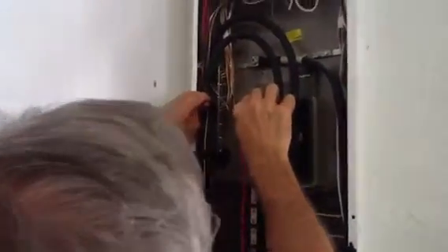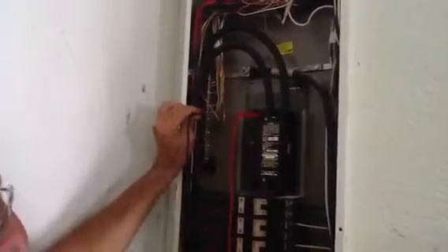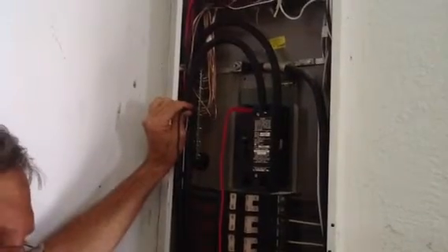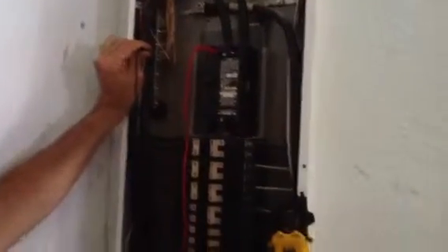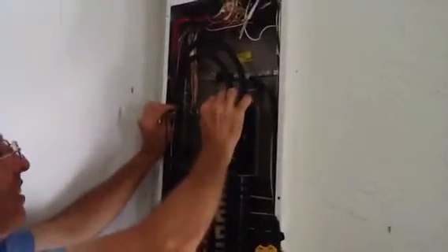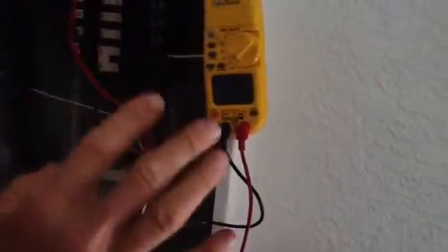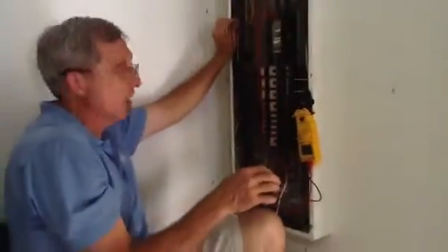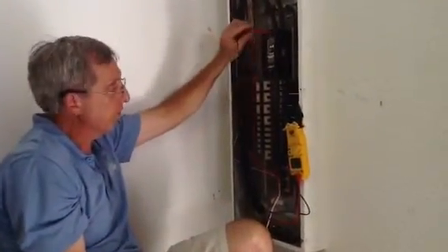Now if you want to make sure you have integrity grounds, let's talk about that. We've already established this is the neutral. I'm going to put my probe over here on the ground bar. You see all these bare copper wires? Those are grounds. The grounds and the neutrals are tied together at the service. So if you look at the meter here, you got 120 volts there. Now I'm going to move my probe out, and I'm going to move it to the other side of the breaker here. 120 volts. That tells me this service is getting the correct voltage. And that's how you determine house voltage. 120 volts to each leg, 240 volts across each leg.